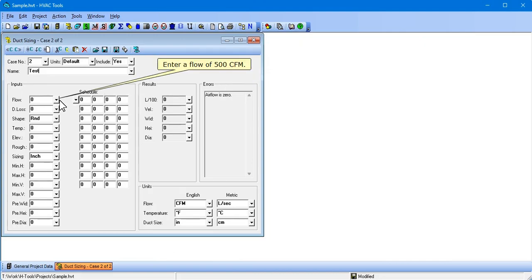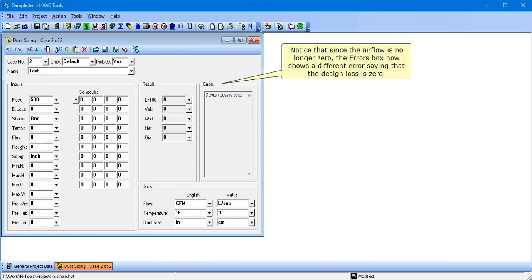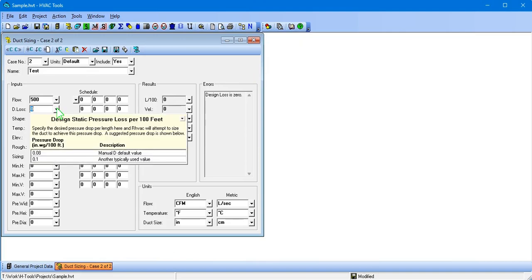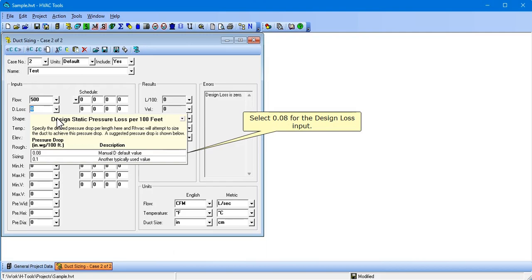Enter a flow of 500 CFM. Notice that since airflow is no longer 0, the Errors box now shows a different error saying that the design loss is 0. Select 0.08 for the design loss input.